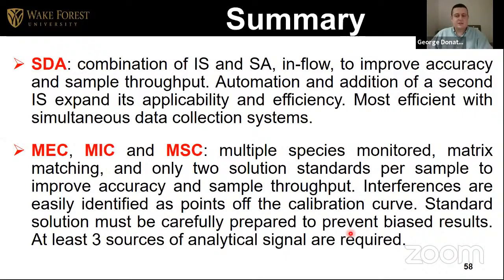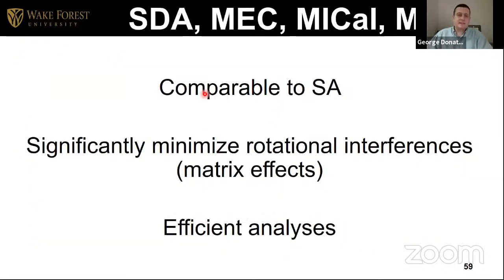The main limitation would be you need to be careful when you prepare the calibration standard. Same thing for SA, because if you mess up that one, you mess up the whole measurement. So hopefully that standard you do with care and the concentration is correct. Then this is kind of the summary of the summary. All of them are compared to standard additions. It can significantly minimize spectral interferences, matrix effects, and you can do efficient analysis.